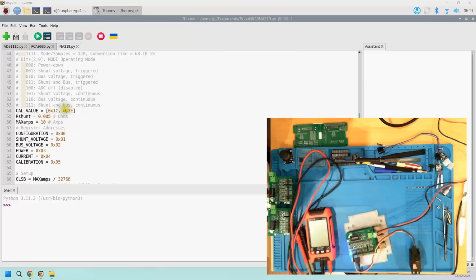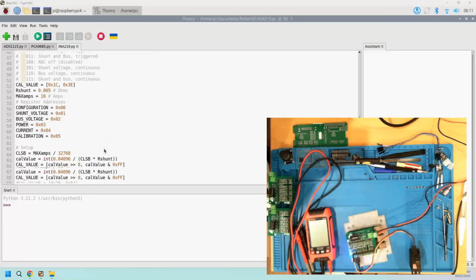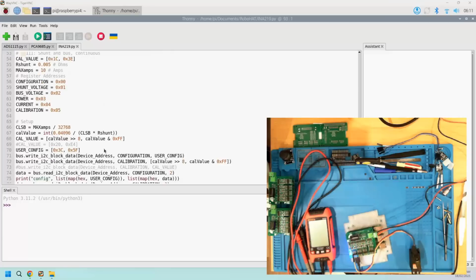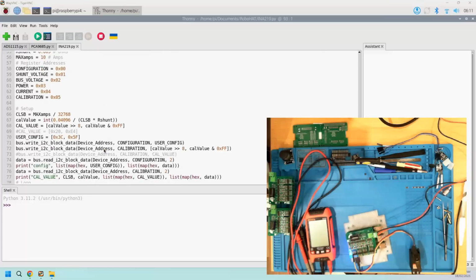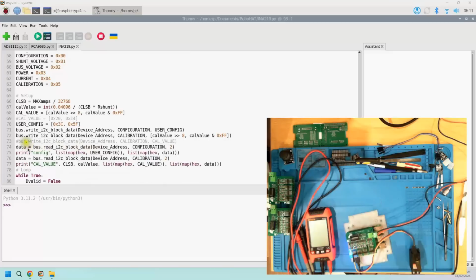We have this calibration value which we use to multiply against, or we tell the chip to use to multiply what it's receiving to give us a value back, and then we can use that same calibration value to actually convert the value we're getting back into microvolts. Alright, so let's have a look at some of the setup. We are going to calculate CLSB. So CLSB is a calculated least significant bit value.